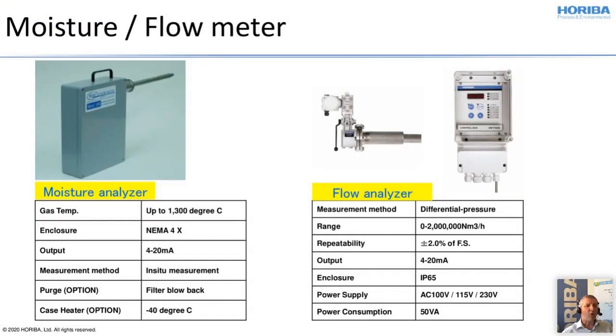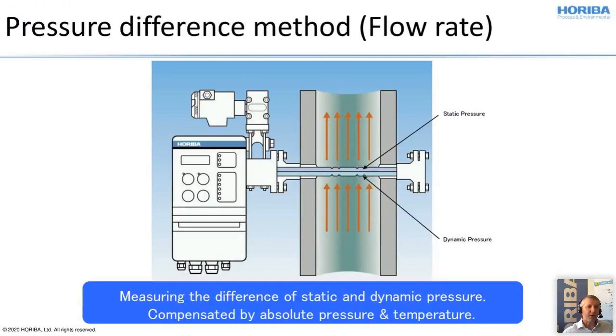To calculate all the necessary relevant data, and also to measure the flow and the moisture in the stack, we have a moisture analyzer and a flow meter available. The flow meter uses the pressure difference method to calculate the flow rate, where you measure the static pressure and the dynamic pressure. The difference of these two pressures gives a signal for the flow, for the speed of the gas. And by compensating with absolute pressure and temperature, you have a standardized normative level of the flow.